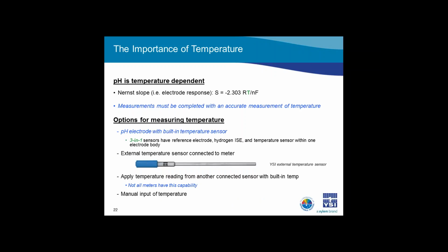Let's discuss why it's important to accurately measure temperature when calibrating and measuring pH. During calibration, we establish the slope and intercept of the millivolts to pH units plot at the temperature of calibration. In order to accurately make pH measurements at temperatures that are different from calibration, we need to adjust the slope and intercept of the plot for the temperature of the sample. The Nernst equation allows for this temperature-based adjustment, and this is carried out by the instrument software. All you need to do is be sure that you are accurately measuring temperature during calibration and subsequent measurements.